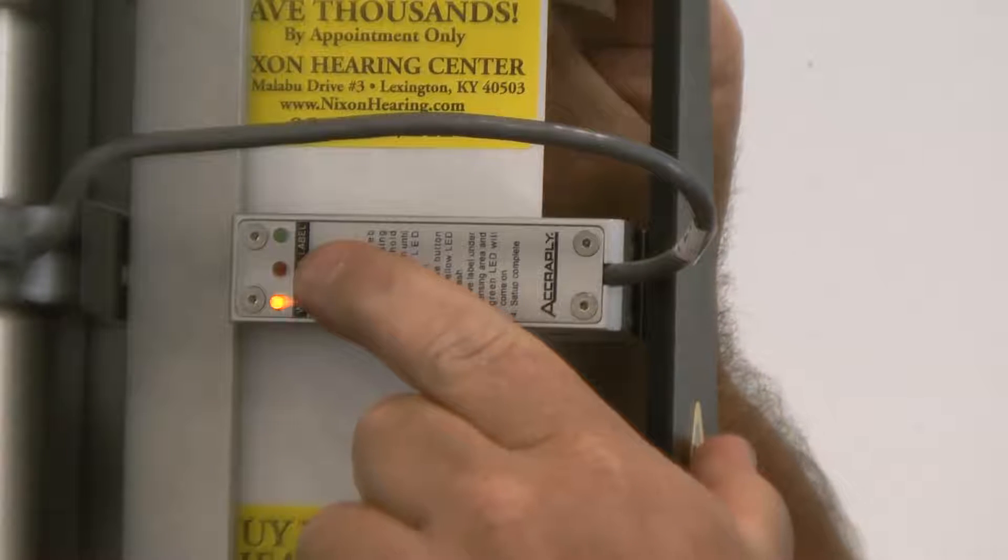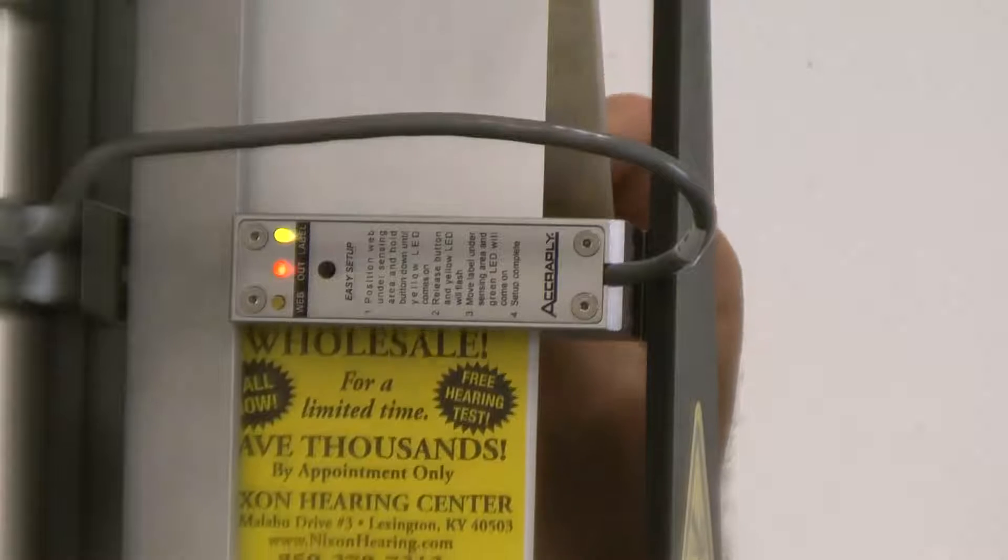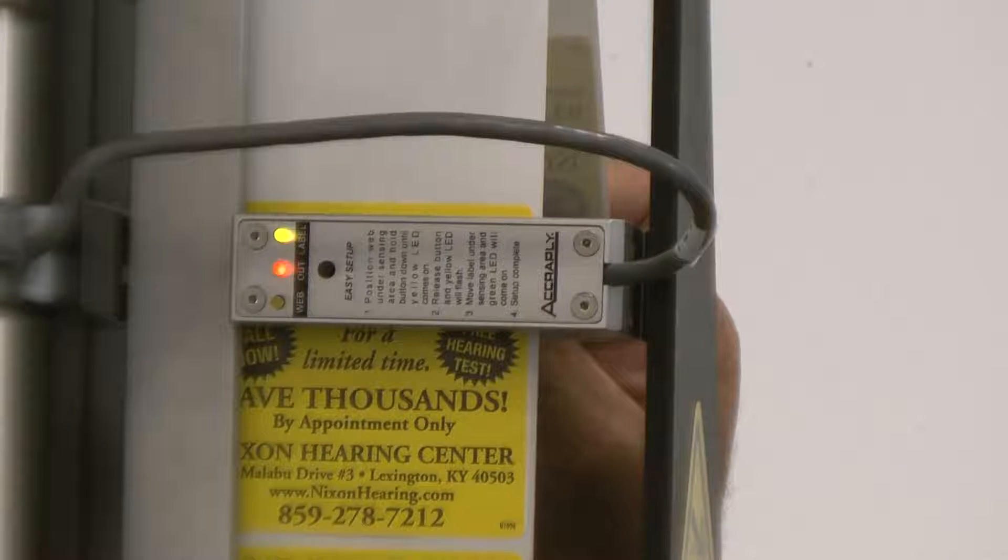Press and hold the button for at least one second. Let it go and the yellow light will begin to blink. At this point, pull the material until the label passes under the sensor. The sensor is now trained.